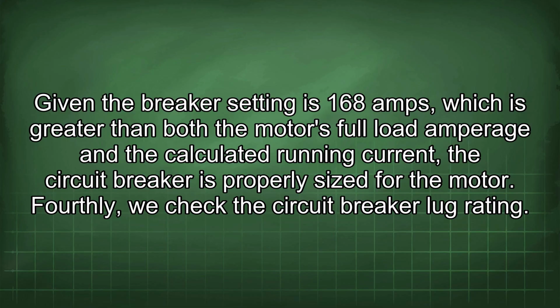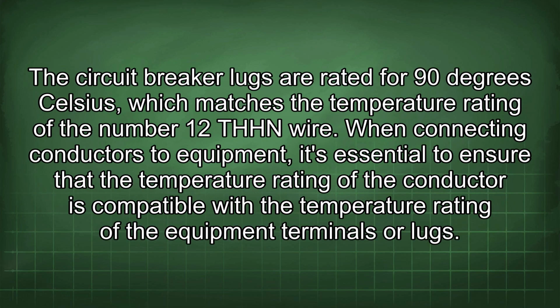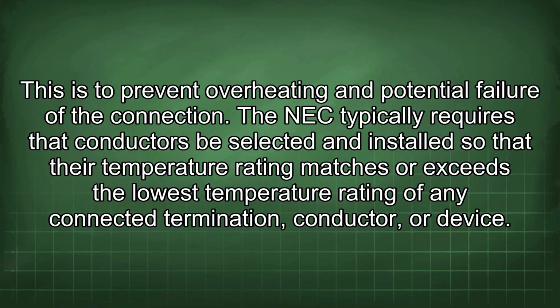Fourthly, we check the circuit breaker lug rating. The circuit breaker lugs are rated for 90 degrees Celsius, which matches the temperature rating of the number 12 THHN wire. When connecting conductors to equipment, it's essential to ensure that the temperature rating of the conductor is compatible with the temperature rating of the equipment terminals or lugs. This is to prevent overheating and potential failure of the connection.